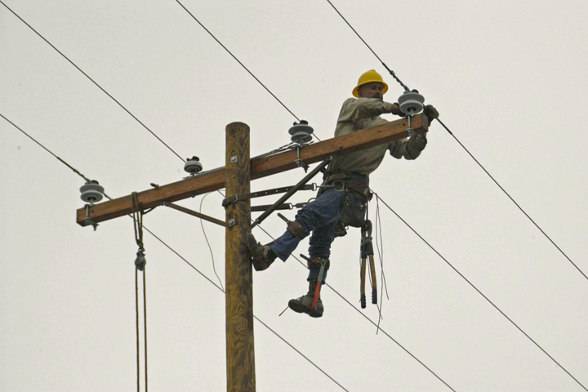De-energized power lines can be hazardous as they can still be energized from another source, such as interconnection or interaction with another circuit, even when they appear shut off. For example, a higher voltage distribution level circuit may feed several lower voltage distribution circuits through transformers. If the higher voltage circuit is de-energized, but the connected lower voltage circuits remain energized, the higher voltage circuit will remain energized. Another problem can arise when de-energized wires become energized through electrostatic or electromagnetic induction from energized wires in close proximity.